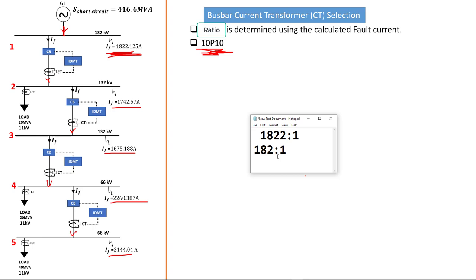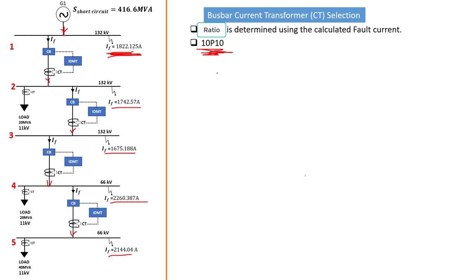You're not going to get a current transformer that gives you exactly this 182 to 1 ratio — there are already current transformers with standard values designed and sold by manufacturers. For instance, for 182, you're going to get a 200 to 1 ratio — this is a standard CT ratio, so that is what you select for the particular bus bar. Your current transformer will give you a ratio error of 10% based on the accuracy limit factor you choose. Even if your fault reaches 10 times the rated value, you're still going to get a 10% accuracy of error, after which the CT will reach saturation and become useless.